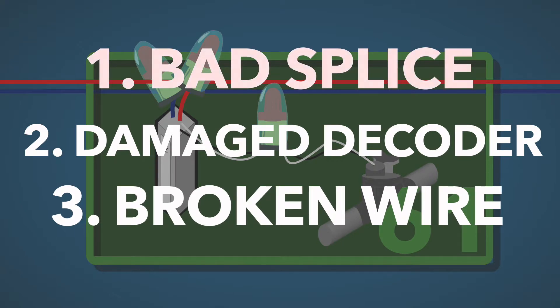The most common culprit will be a bad splice. If your problem is just the single valve, your issues could also be the valve itself, the valve splices, or the solenoid.